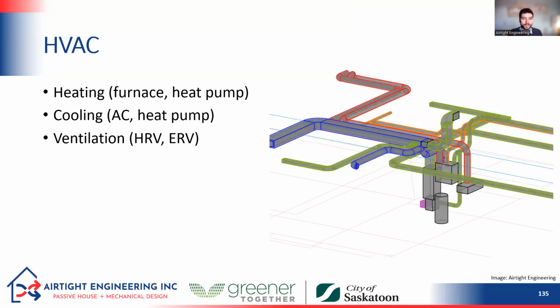Moving on from the envelope, we can also do a lot with our HVAC system. So in terms of heating, if we've got older gas appliances, for sure upgrading to new high efficiency appliances is going to make a big difference, because even if your gas appliance was rated at 80% efficiency when you installed it, if it's 25 years old, chances are it's operating at a much lower efficiency than that. So maybe it's 65% efficient at this point. Who knows? So replacing with a high efficiency, 95% or above, that's going to be a huge energy savings.